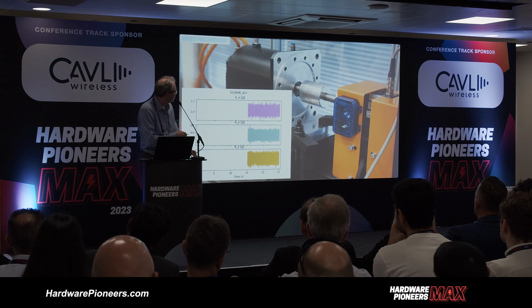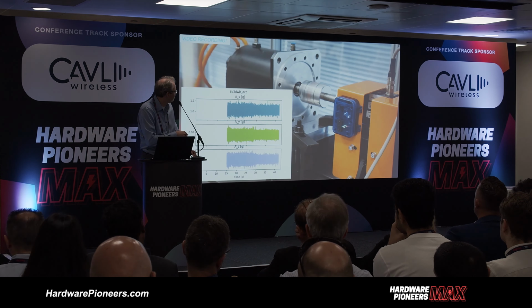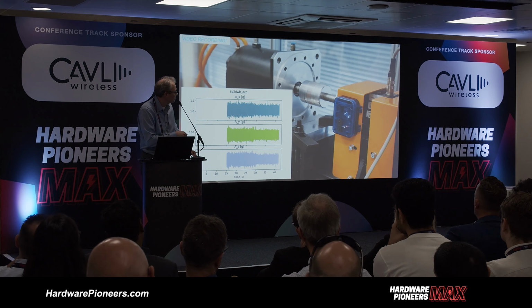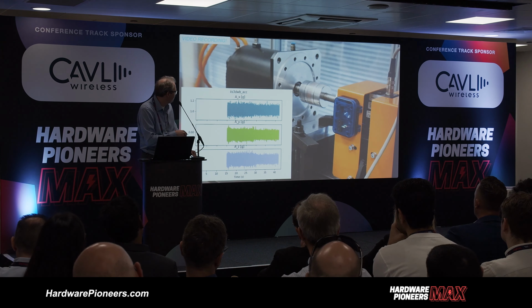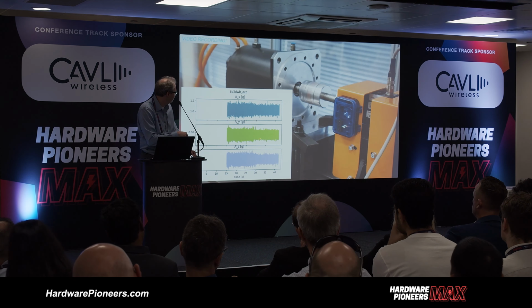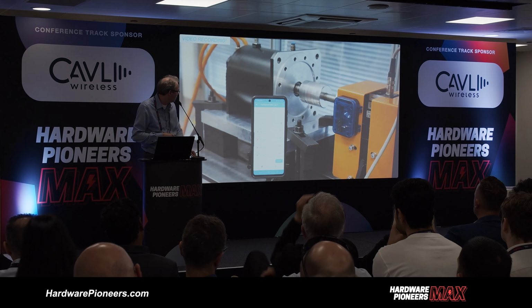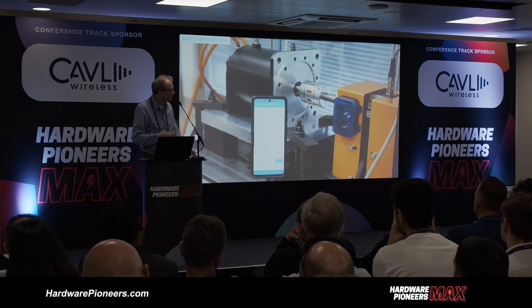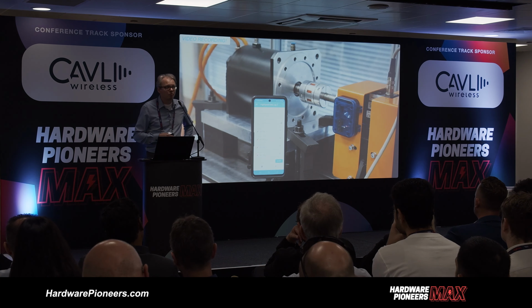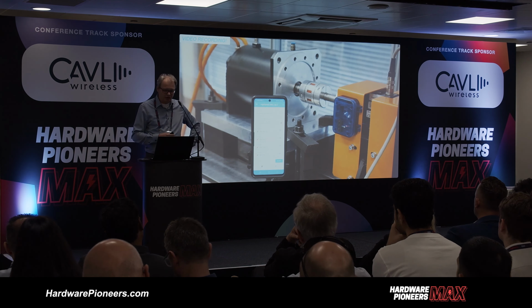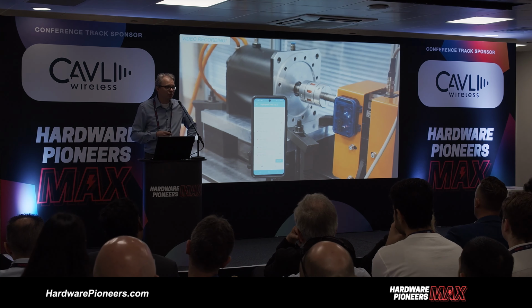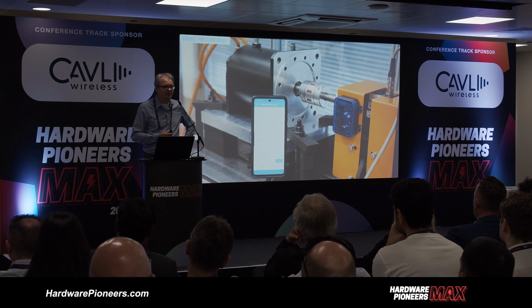And shortly we are adjusting then the speed of this motor in here. You can see that it starts to run with slower beats, and then you start to see in here basically the vibration level is getting lower. So we are highlighting this because in normal applications it's very difficult to know what kind of vibrations you might expect. So really making this kind of test in the very beginning is the easiest way to get started.